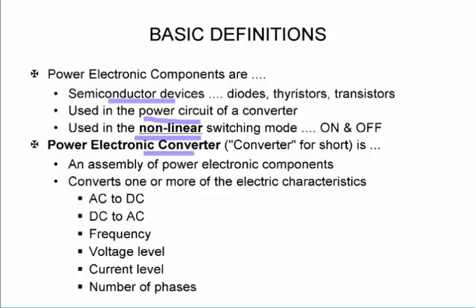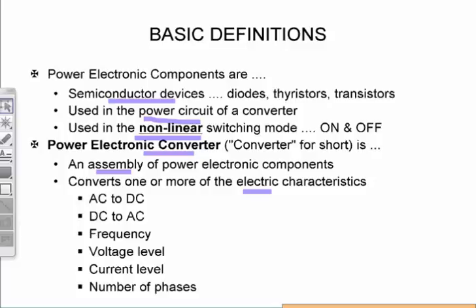The power electronic converter is an assembly of the power electronic components and it will convert one or more of the following electrical characteristics: AC to DC, DC to AC, it might be a change in frequency, voltage level, current level, or even the number of phases. So it can be a single phase supply and if it is a variable speed drive it can have a three phase output to drive the motor.